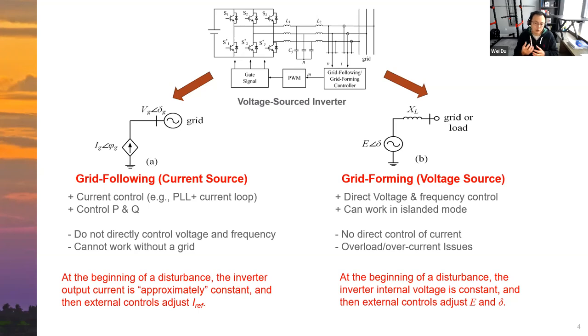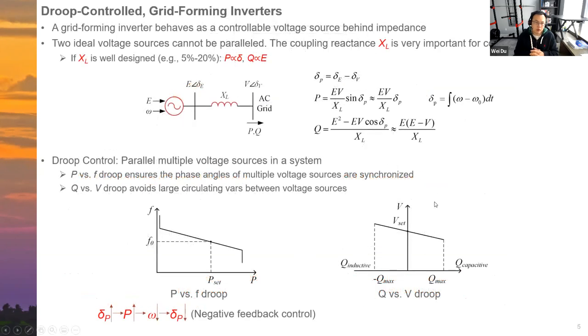This is more like a synchronous machine. And then there are some external controls that adjust the voltage magnitude and phase angle, such as the droop control. So then I'll talk about droop control for grid forming inverters, because as mentioned, the grid forming inverter behaves approximately as a voltage source.